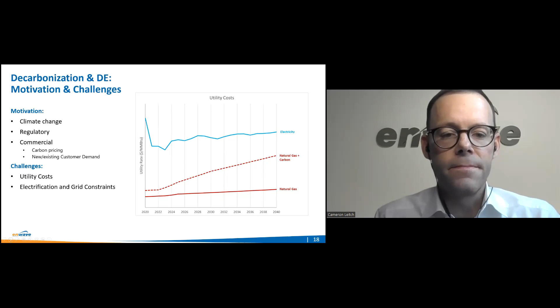Based on the foregoing slide, it becomes obvious that a one-to-one replacement of existing fossil fuel-based boilers with electrical boilers isn't going to solve the most challenging problems. In many municipalities, the market cost for electricity may be considerably higher than their fossil fuel equivalents. And except in those locations with abundant and low-cost electricity, it's unlikely that electrical utilities will be able to accommodate the significant demand increase imposed by a transition to electric boilers. Heat pumps help overcome these issues by the multiplying effect of energy input to energy output if one has an available and adequate heat source. This multiplying effect is represented in the unit coefficient of performance, or COP, and it directly and proportionally improves production costs, reduces GHGs, and more fully leverages the electrical capacity from a potentially constrained grid.